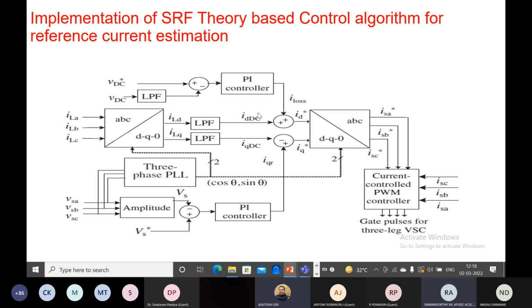Now the PI controller output gives the loss component in the inverter, and this becomes the active component from the load side. Similarly, we get another component, the reactive component from the load side. For generating the source reference, we add loss and active. The plus sign is very important, it is not like anyone can use plus minus, minus plus, or minus minus. You have to keep plus plus.